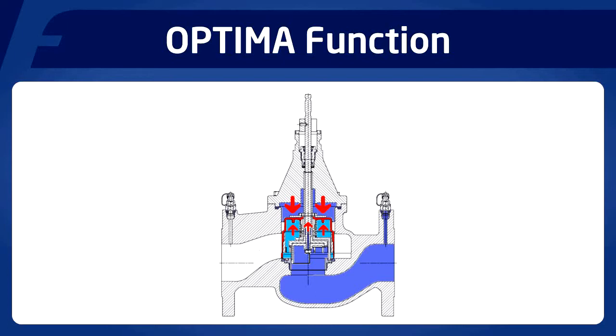That balanced force will set the position of the outlet of the valve, which means as the water flows through the outlet and onwards and downstream, the remainder of the additional pressure is now lost, and therefore the pressure difference between upstream and downstream can vary, but the pressure difference between the upstream and the internal to the valve remains constant, critically, across the controlled element of the valve.